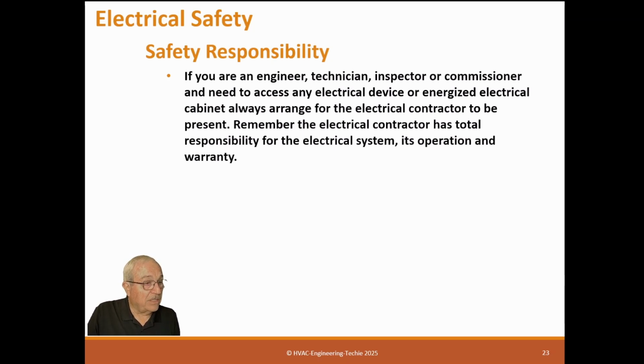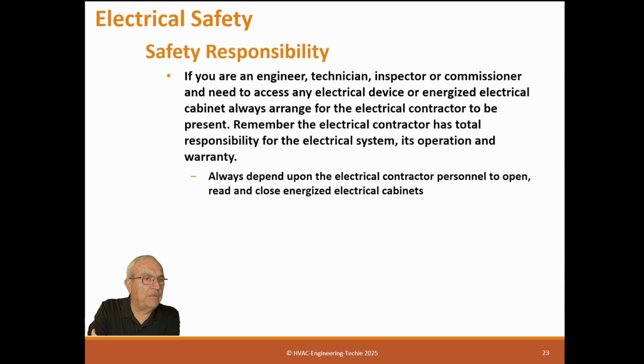Now, you can actually enter a panel if they say it's okay and you're there with them, then you could do that. My advice is always, if you're in construction, have the electrician open the panel. And if you have a complicated reading, let him take the reading for you. It's just the way things should be. Always depend upon the electrical contractor person to open, read, and close energized electrical panels. Never assume the safety responsibility of the electrical contractor.